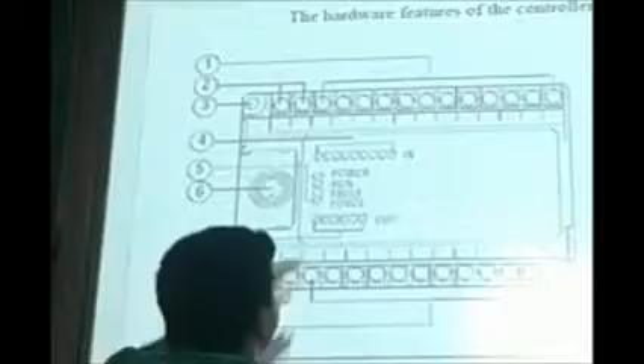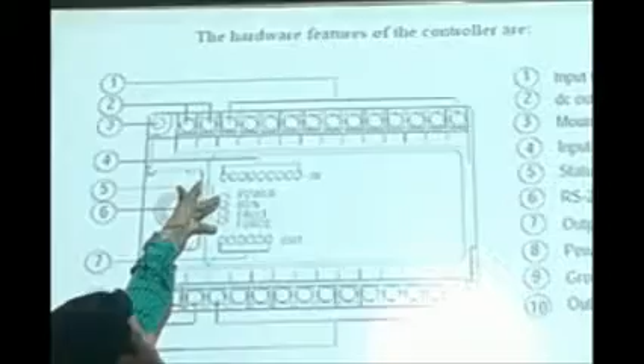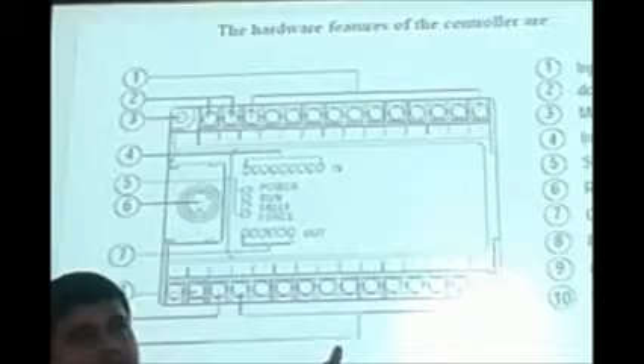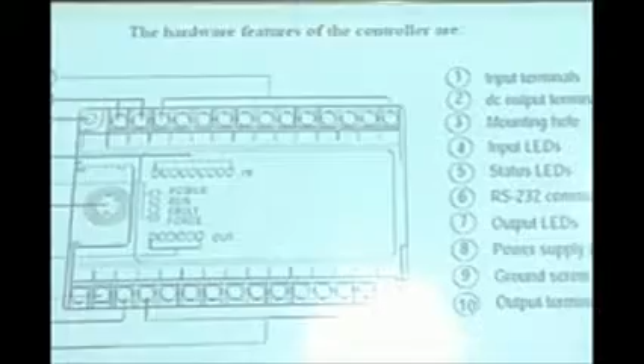Next we will see the hardware features of the controller. See, here is what I am saying. This is the PLC. Here are inputs and outputs. Here also some LED indicators are there. Power: when the PLC is on, the LED will glow. Second, run: when the PLC runs, it lights up. Then fault: if there is any problem in the connection or any plant sensor, it shows fault. And force: sometimes I want to force some program. I know that it is correct, but sometimes the software shows an error that it is problematic, so I will use this.